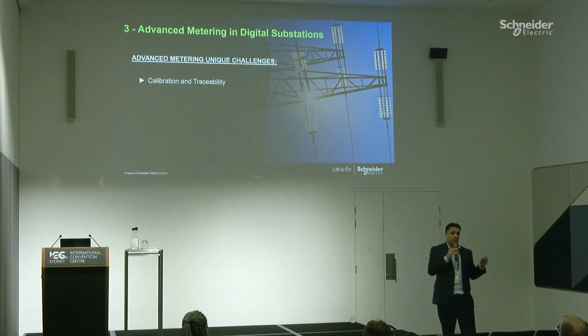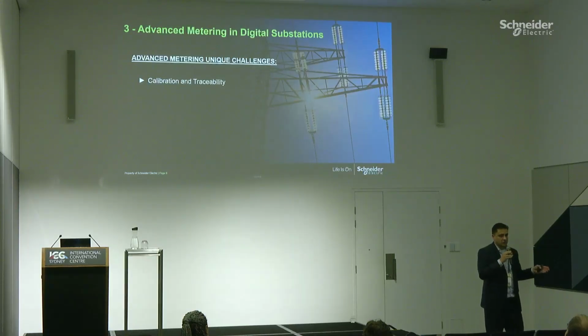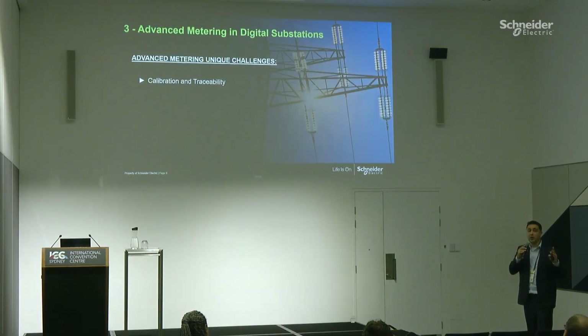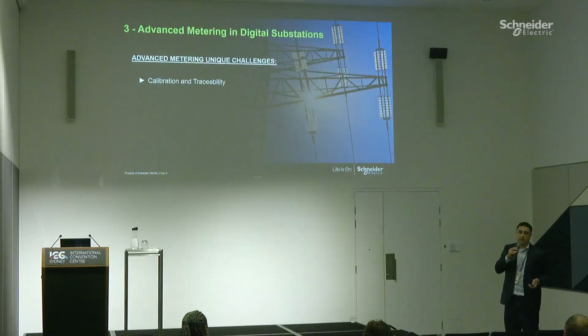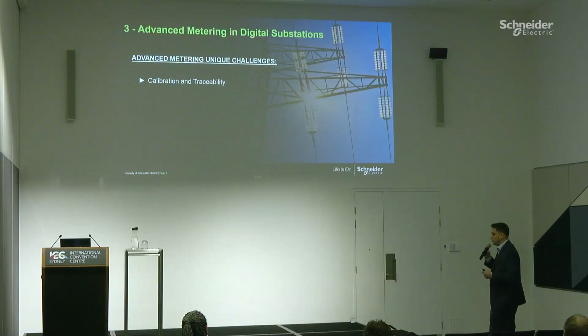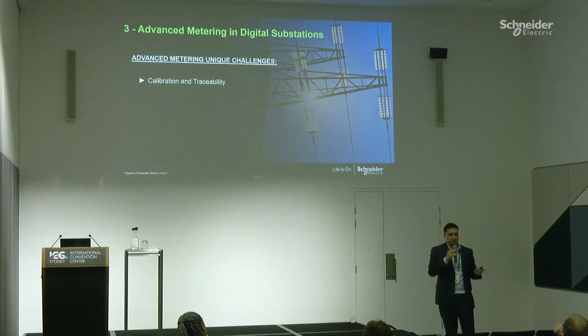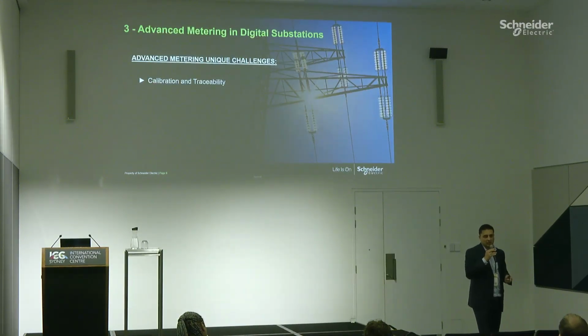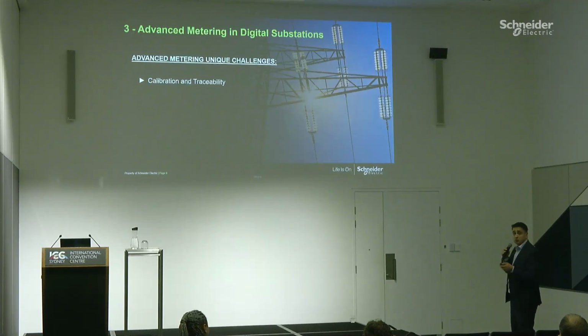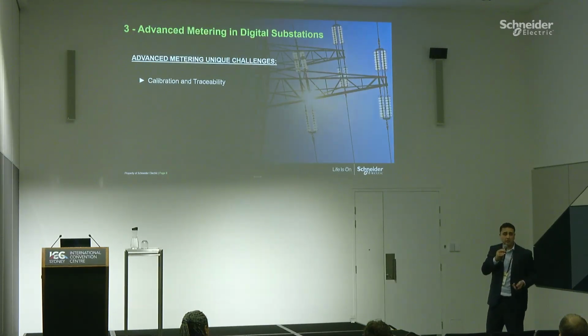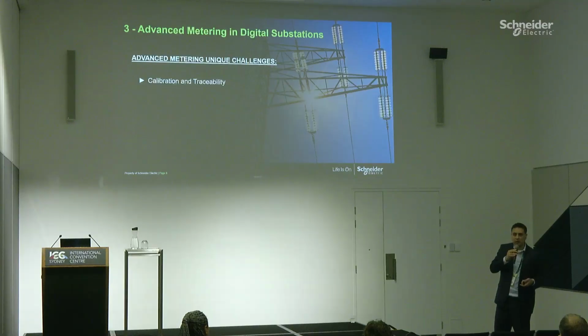So now that you are separating the analog to digital conversion from the calculator, what needs to be calibrated? Do we need to calibrate the merging units? Do the merging units meet the same level of accuracy that we have today with advanced meters? Do they meet that accuracy over time? That's the long-term stability topic I mentioned before. Those are open questions right now that we're working with our customers and regulators to understand how we can solve those.